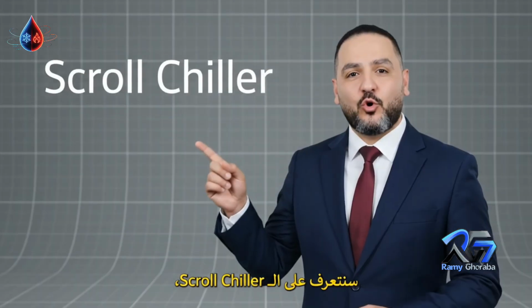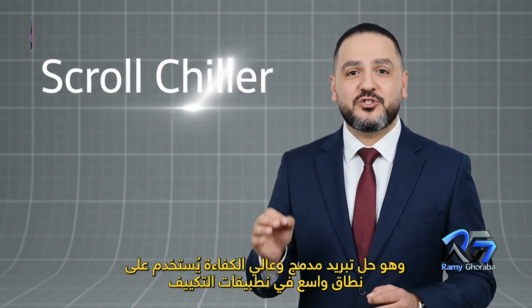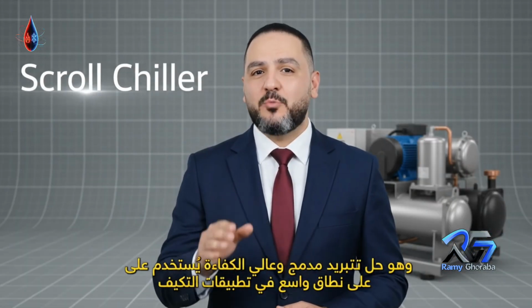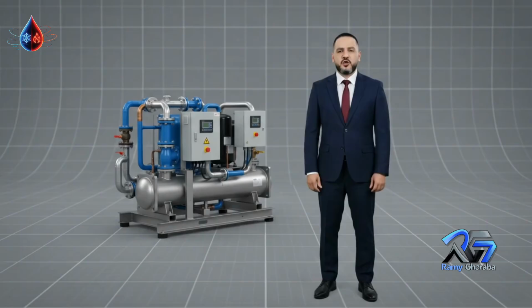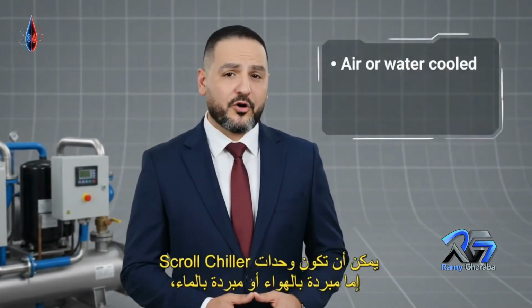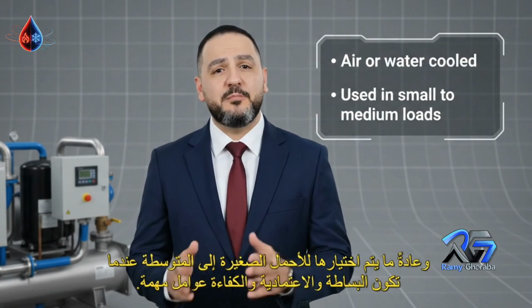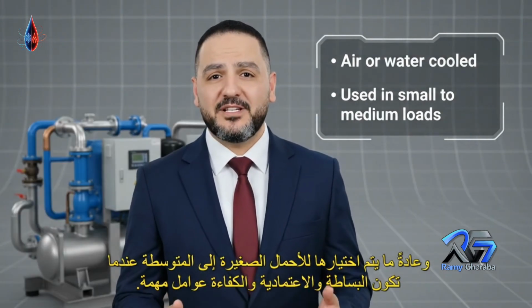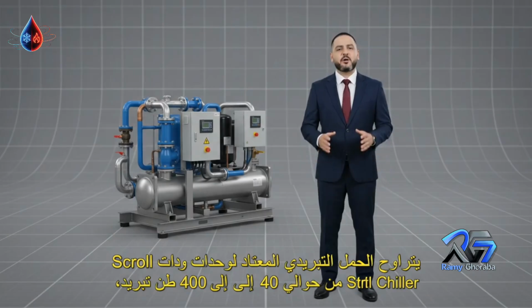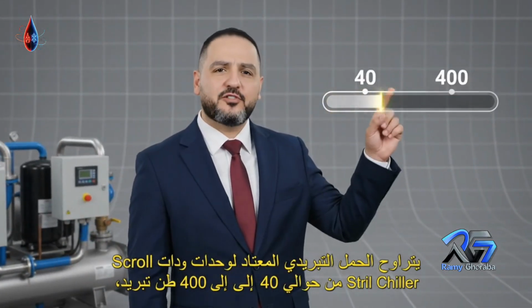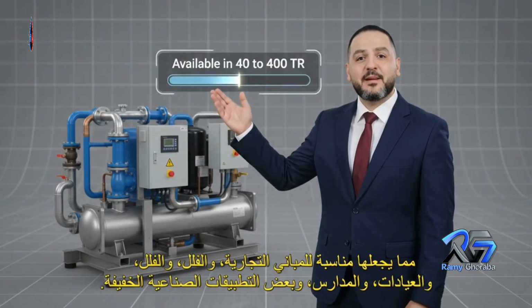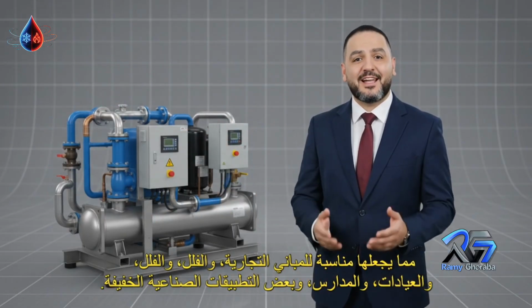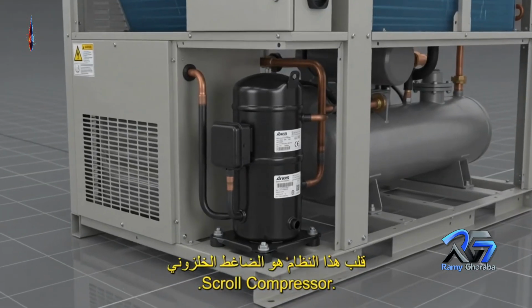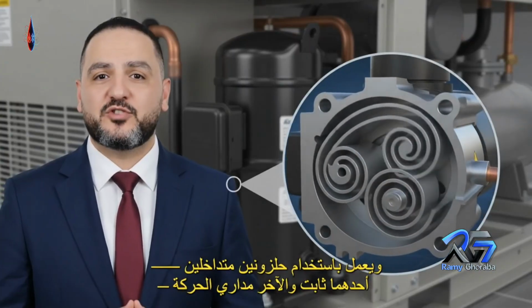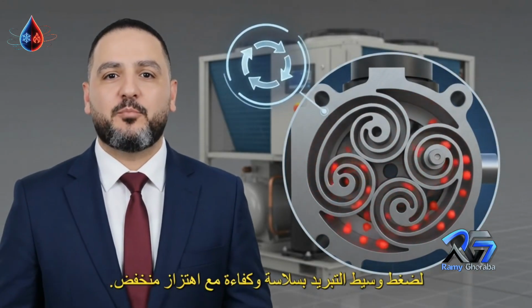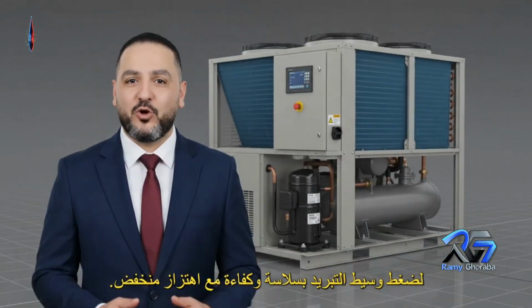We're exploring the scroll chiller, a compact, efficient cooling solution widely used in small to medium HVAC applications. Scroll chillers can be either air-cooled or water-cooled, and they are typically selected for small to medium cooling loads where simplicity, reliability, and efficiency are important. A typical capacity range for scroll chillers is about 40 to 400 tons of refrigeration, making them ideal for commercial buildings, villas, schools, and light industrial facilities. The heart of this system is the scroll compressor. It uses two interleaved scrolls, one fixed and one orbiting, to compress the refrigerant smoothly, efficiently, and with low vibration.